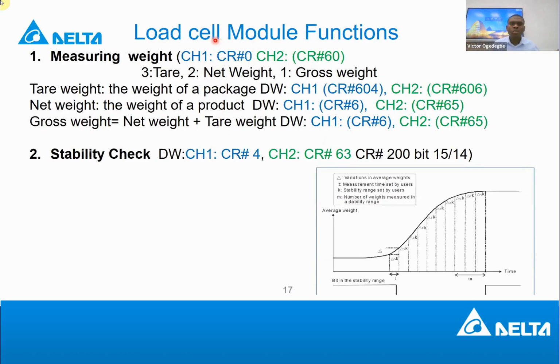Maybe 1 kg is equal to 1,000. 2 kg is equal to 2,000. In the stability check, you can specify which range of measurement you want to take as meaning that if I'm reading this value, my measurement is stable. If you set that up in channel 1 with this register, or in channel 2 with this register, then when the measurement from the sensor, the digital value in the load cell module, is in this range, there's a control bit 15 and bit 14. Bit 14 is for channel 1, and that bit will be high. So it's like a flag. You can read it with 2 instructions. If you see that bit, it means that what I'm reading is still balanced.